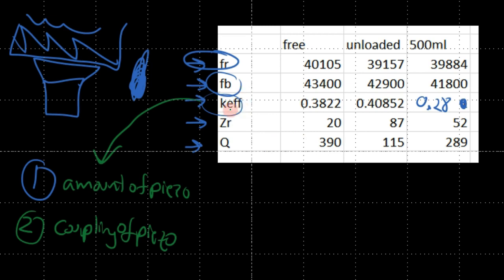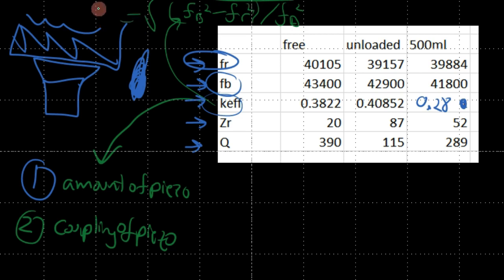And sorry, I forgot to mention the equation for the coupling factor, which is FB squared minus FR squared, all divided by FB squared. And this gives a general understanding of the coupling. And you have to put that all under a square root. And then you have the effective coupling factor. This term generally, for this case, is an effective coupling factor. For other geometries, you can analytically calculate it, especially for geometries where the piezoelectric material is the only thing there.